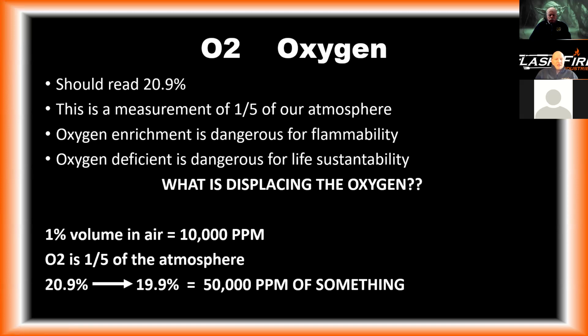If I told you that basement has 50,000 parts per million of carbon monoxide, you're going to be masked up, and you know that anyone down there is probably dead if they've been down there for any period of time. And yet here we are with our oxygen sensor. It hasn't even alarmed yet at 19.9%, and we could potentially have 50,000 parts per million of something in the basement. So all I'm trying to get across to you is, just because your meter's not alarming, make sure you're keeping an eye on this oxygen sensor. And if you're going down into a basement or into an enclosed area and it starts to move, you need to consider that you're going into a highly hazardous atmosphere.